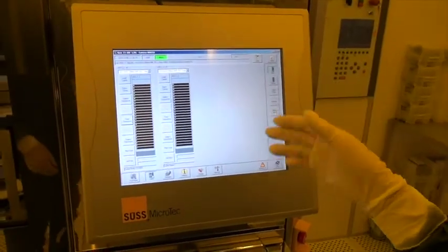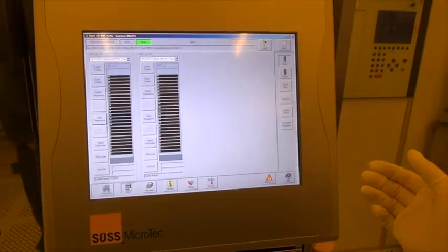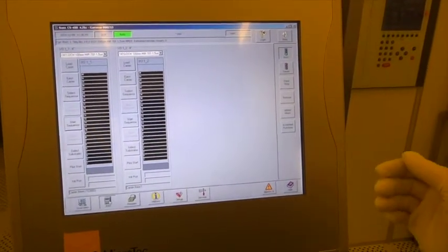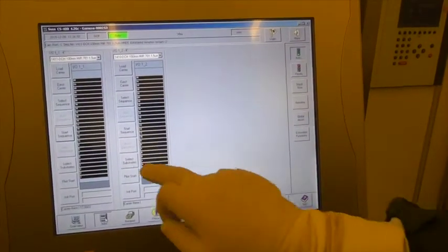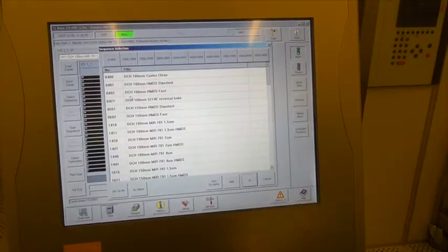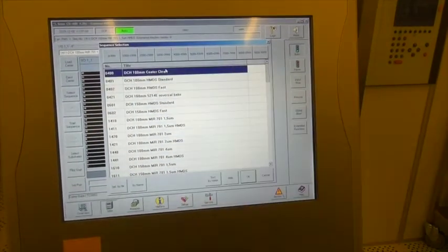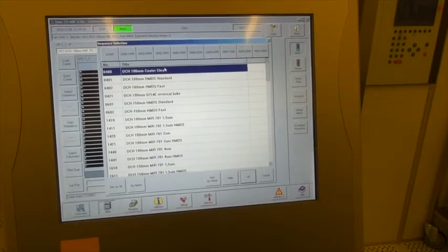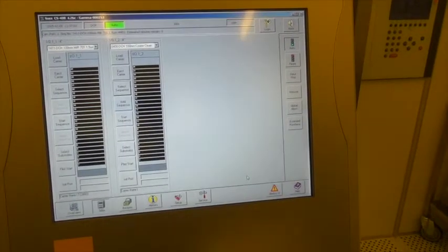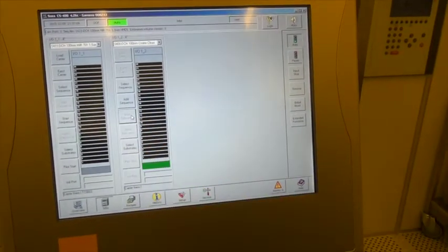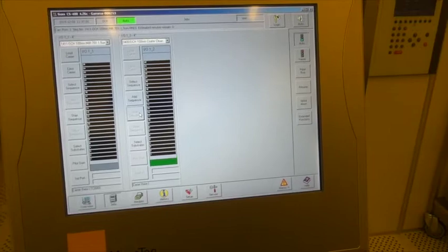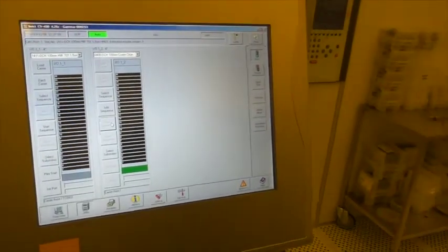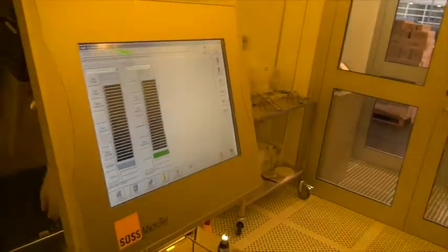For this particular sequence that I'll be running now, the cleaning sequence, I don't need an output carrier. So I will just select the sequence here. It's the first one on the list, it's called Coater Clean. And press start sequence. It will now automatically load the cassette first and then run the wafer.